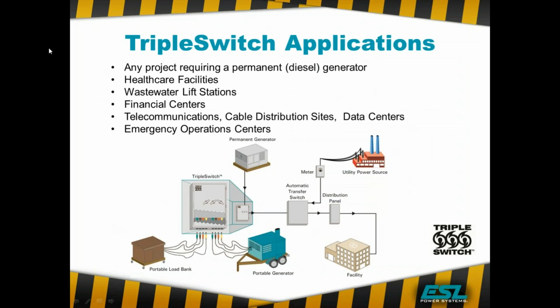So your triple switch is going to be used pretty much anywhere where you have a permanent diesel generator. We have done some triple switches with natural gas generators. They typically don't need to be load banked quite as efficiently or often as a diesel generator.